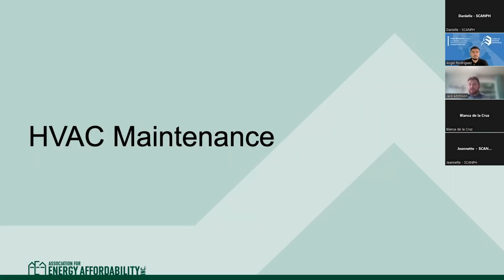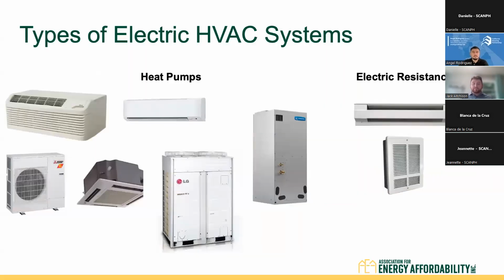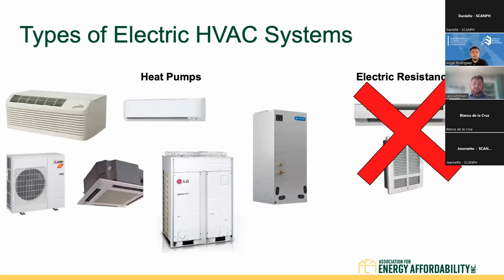So jumping right into HVAC maintenance of all electric HVAC systems. Next slide. So there are two main types of HVAC systems that are all electric that we're going to see in buildings. We have heat pumps and we have electric resistance. Next slide. We should be really focusing just on heat pumps. Electric resistance is no longer code compliant in California. And heat pumps are really the catalyst to electrification and decarbonization in California due to their increased efficiencies. And because of those increased efficiencies, that's really where we're going to see cost savings and potential utility savings.